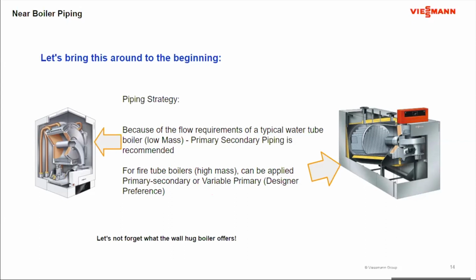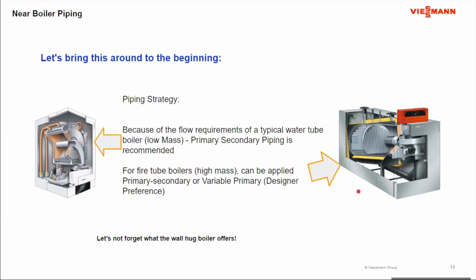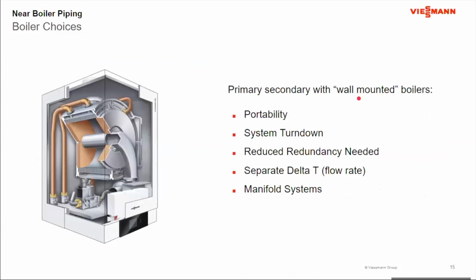But when we start to do this, particularly in areas where the alternative options could be either wall-hung boilers or floor-standing boilers, there are other items that make the wall-hung boiler much more attractive. Okay, so with the wall-hung boilers, because they are compact, there are a lot of things that we look at and say, you know what, these make great sense to use instead of floor-standing boilers. First off, these wall-hung boilers are very portable. So they're easy to get in and out of the mechanical room. I don't have to worry about doors. When I look at stairwells, I don't have to worry if there's a 90-degree turn halfway down where I can't get a larger floor-standing boiler.